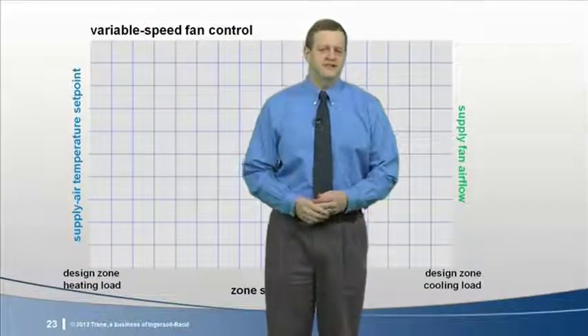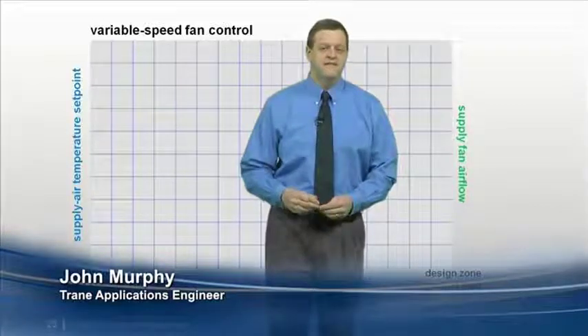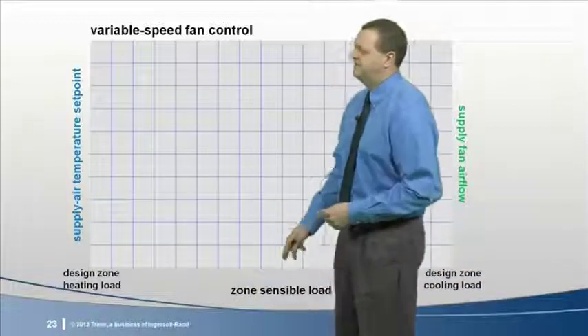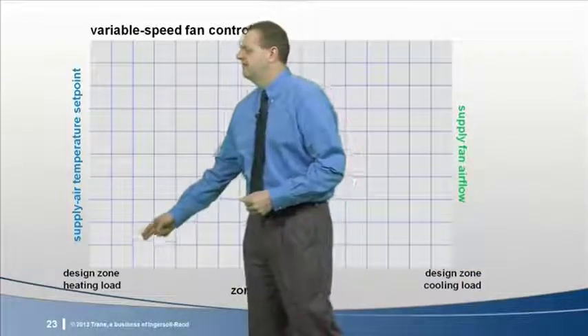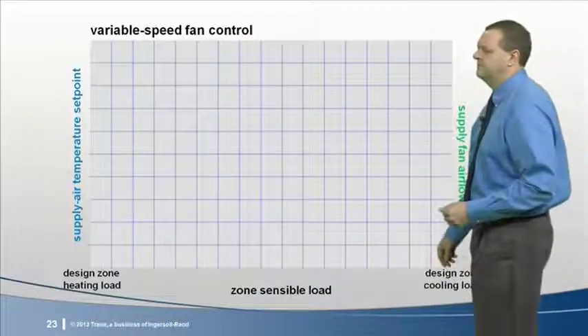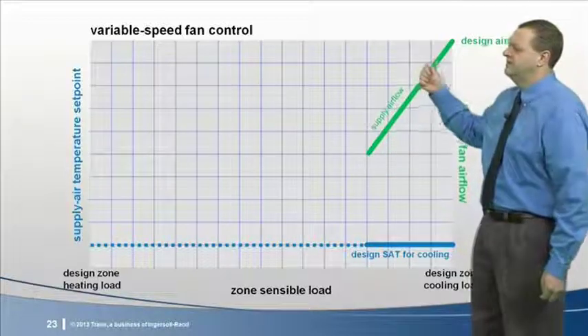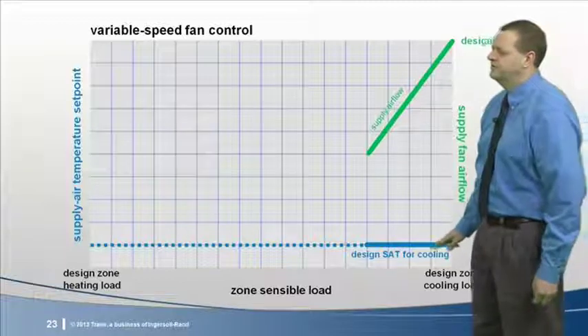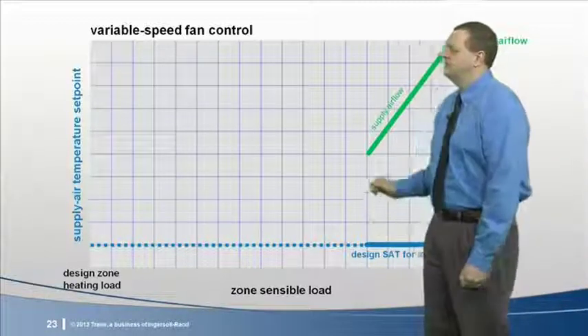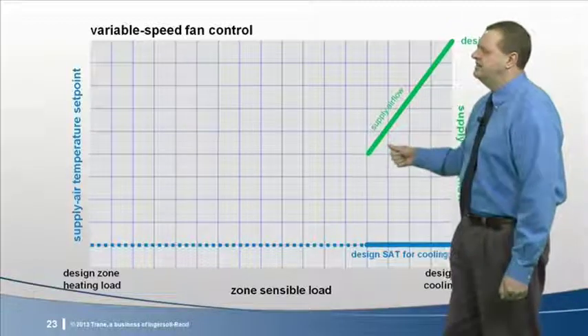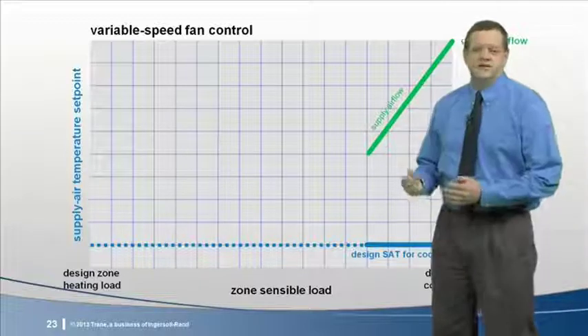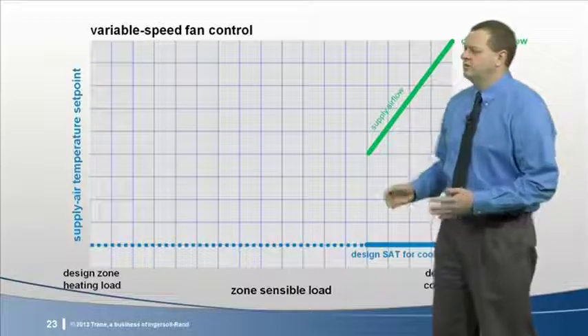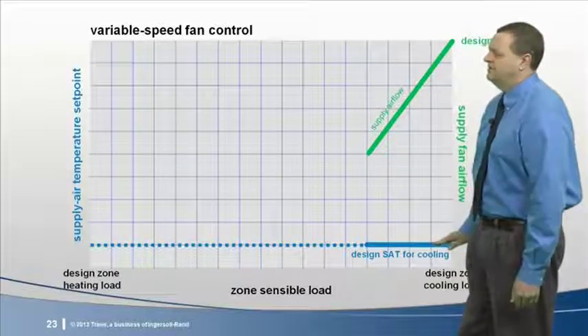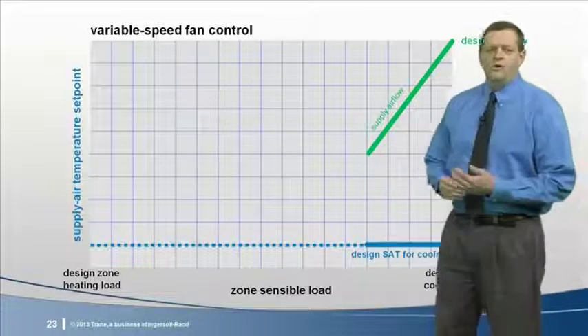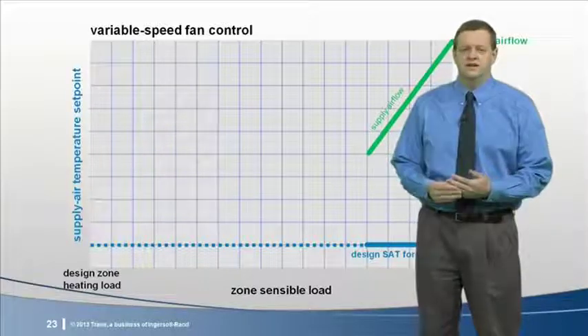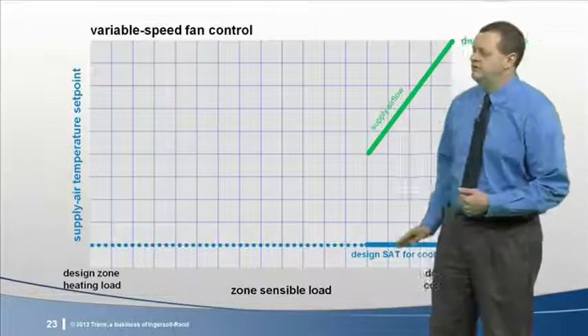This chart depicts an example control sequence for a Single Zone VAV system, which uses a variable speed fan. The x-axis is the sensible load in the zone, with design heating load on the far left and design cooling on the far right. When the zone's at design cooling load, this system delivers maximum supply airflow at the design supply temperature for cooling, 55 degrees for example. As the zone cooling load decreases, supply airflow is reduced as needed to maintain the desired temperature in the zone. This is accomplished by varying the speed of the fan motor. Cooling capacity is then staged or modulated to maintain the supply temperature at the same design set point. Or if the system has an airside economizer, depending on outdoor conditions, the economizer may provide all or part of the cooling to achieve this temperature.